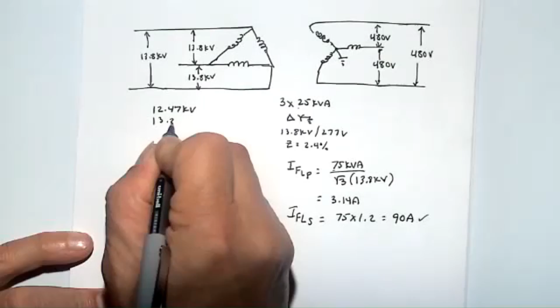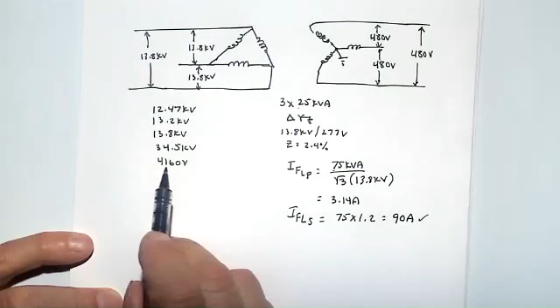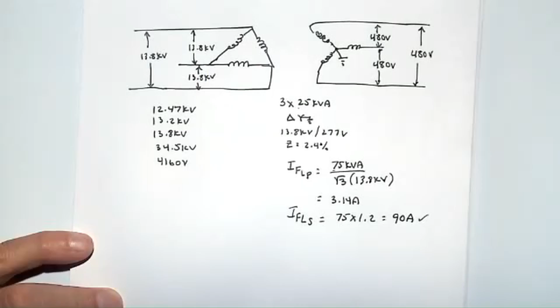Okay, now why am I using 13.8 kV? I could use 12.47 kV for medium voltage. I could use 13.2 kV. I could use 13.8. I may even go as high as 34.5 kV for medium voltage, and I might go as low as maybe 4160 volts or 4.16 kV. But anyway, or even 2.4 kV. But the point is, I'm trying to be consistent, so I'm using the 13.8 for this calculation. So again, you can see what our load currents are going to be primary and secondary.